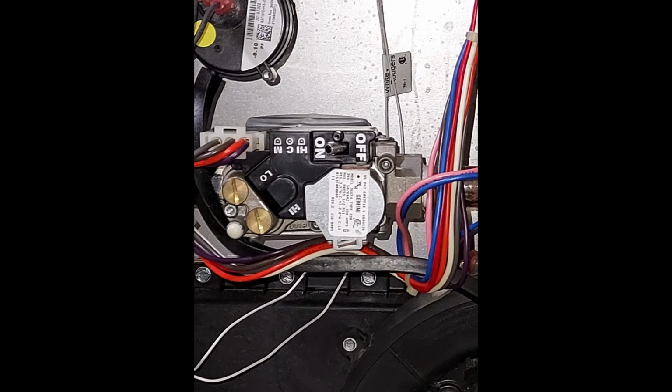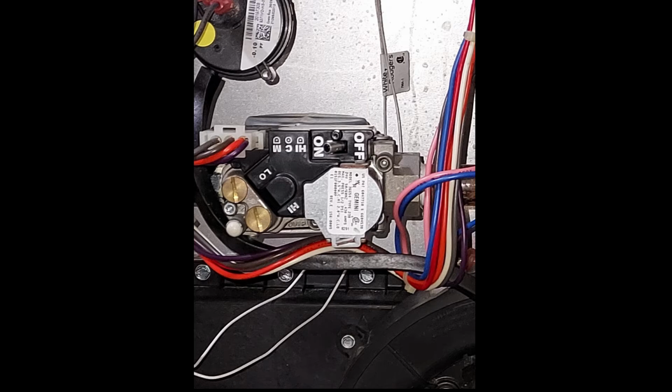Okay, this is the gas valve. It operates off of 24 volts, and this is what will open after your igniter comes on and glows red hot. This will open, shoot gas through the burners and ignite, and that's where your heat comes from. This one is actually a two-stage, so it has a high flame and a low flame that can both be adjusted to the appropriate gas pressures. But yeah, your gas valve, again, they look different in different models, but as long as you can identify it, you'll be able to troubleshoot it with the help of my future videos. We're going to go over live troubleshooting of all these components.